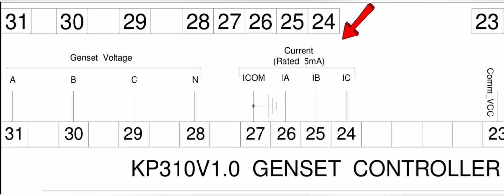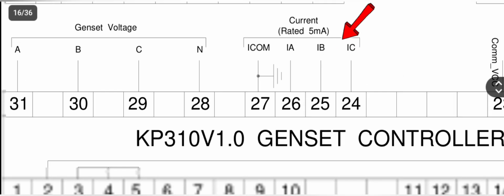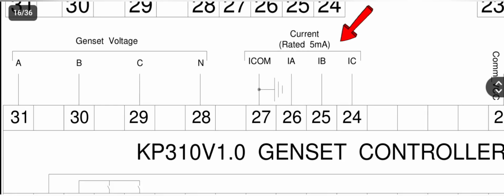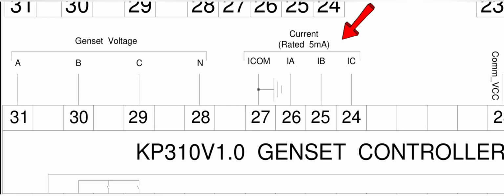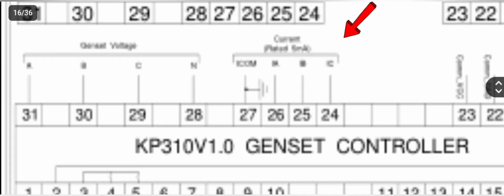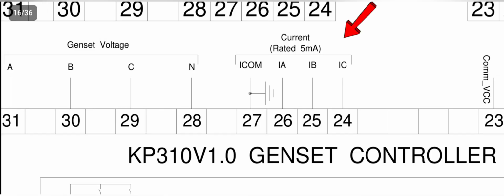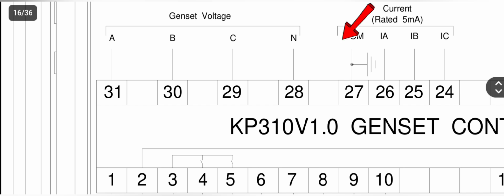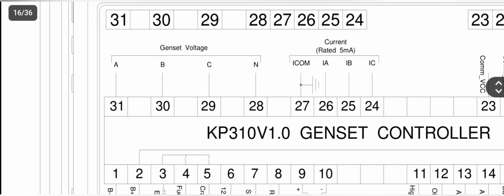Three CTs. As you can see here, ampere A, ampere B, ampere C. These three are used for the current transformer, three CTs with four wires. One is the common of the three CTs and one is a single main wire. That means this is the current transformer input.